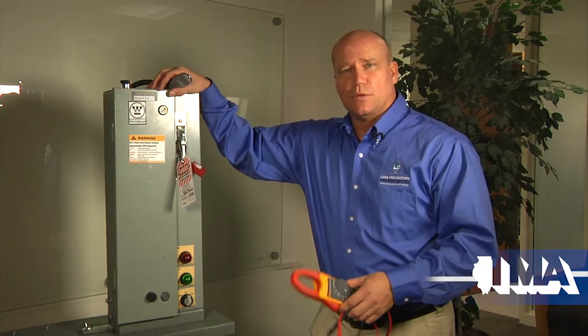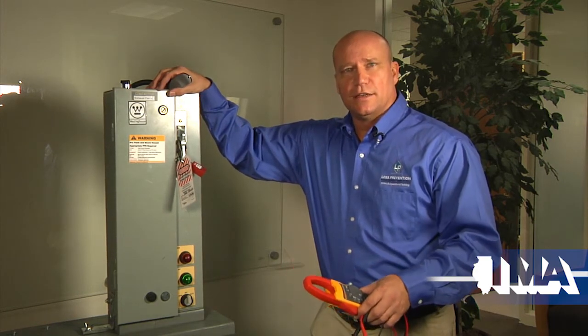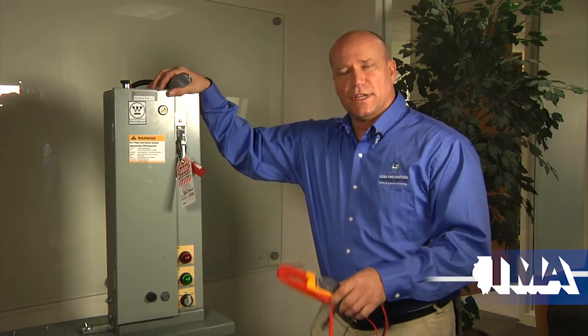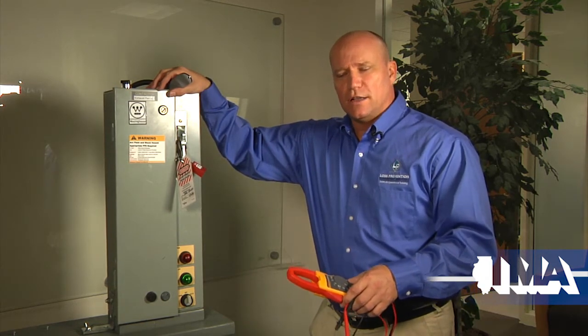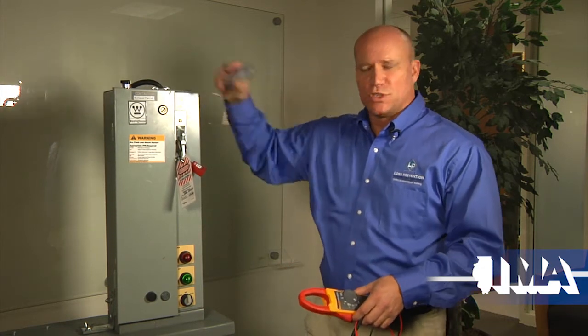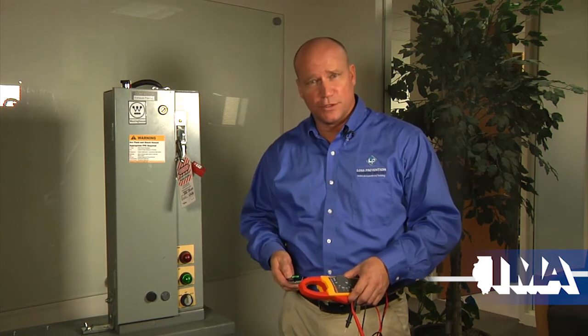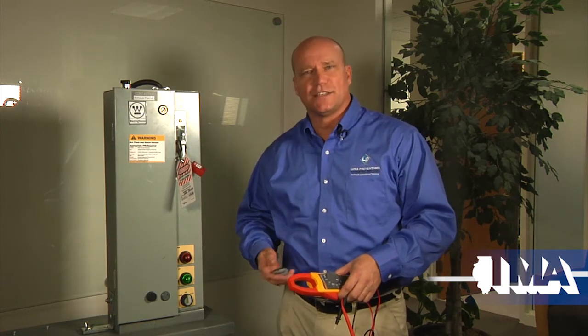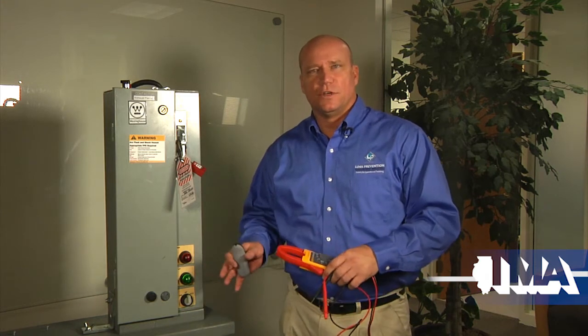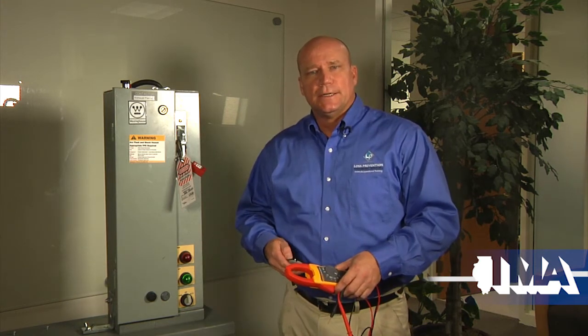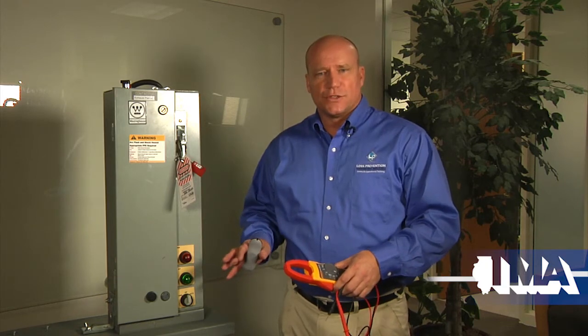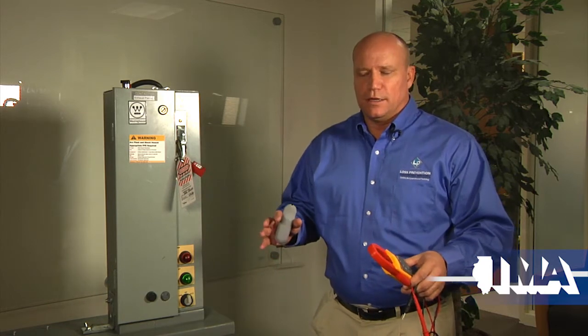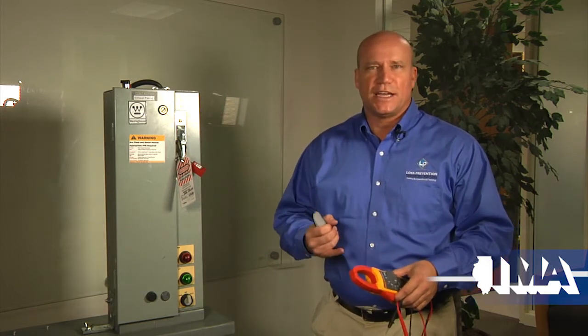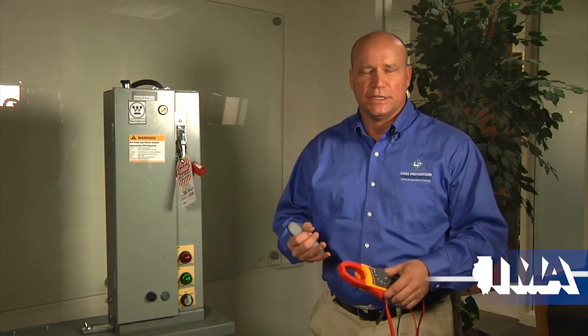That's one aspect of today I want to get through, to make sure you understand the process of selecting the appropriate levels of personal protective equipment, not only for shock but also for arc flash, which is required anytime you open a piece of equipment that has potentially live terminals or parts. The process we're going to talk about, when you put a meter on before you touch it, is a test before touch. On the aspect of boundary controls, I don't have the boundaries established here, but they should encompass both the shock protection and the arc flash boundary protection zones.